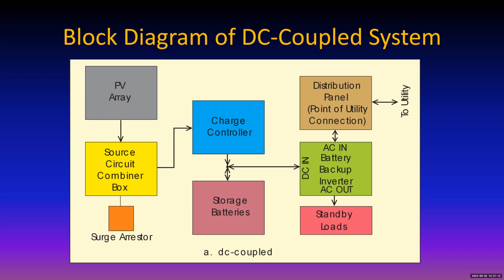Upper left-hand corner: solar array, making electricity. Then the source circuit combiner box. Why is that? Typically your solar array is limited in what voltage it can run at, so one string of modules, say a string of 400 watt modules, may only produce 4,000 watts. If you want 12,000 watts, you'll need 3 of those strings in parallel; for 16,000 watts, you'll need 4 in parallel. So you run those strings into the source circuit combiner box.